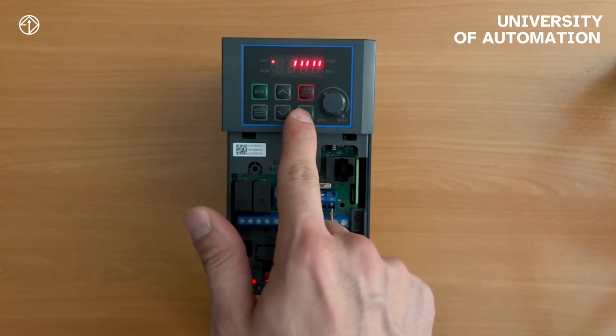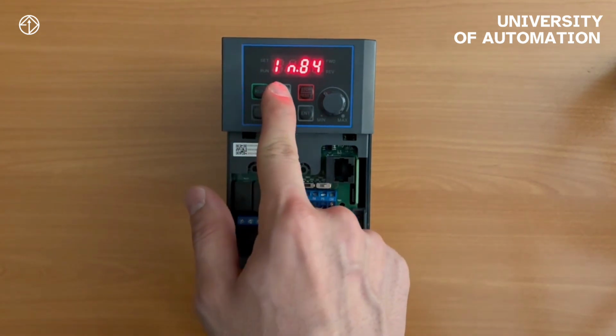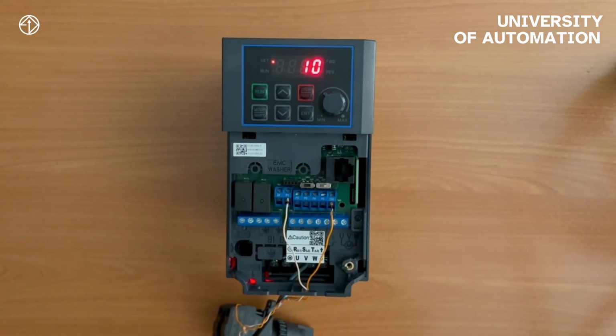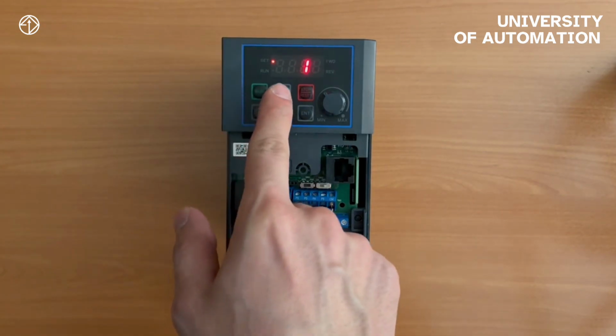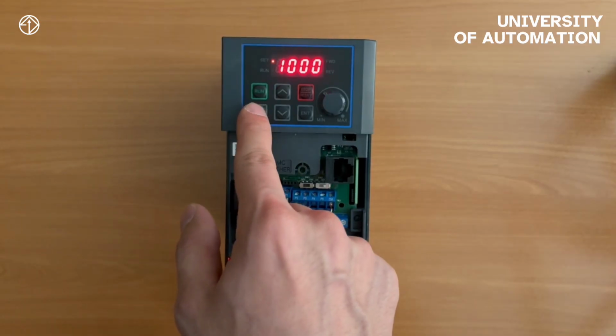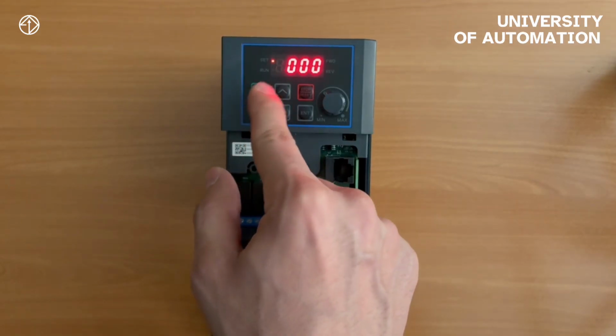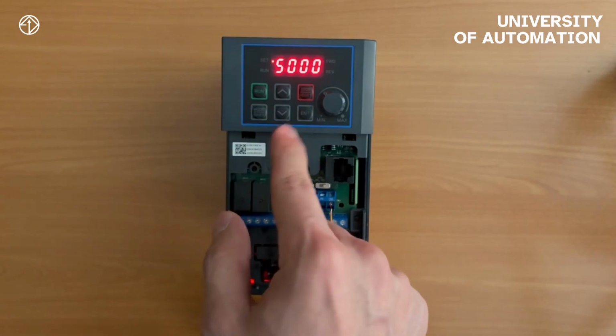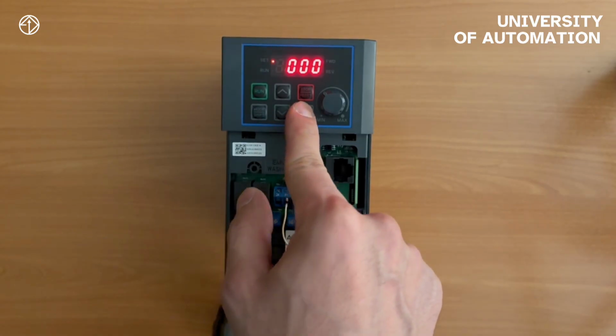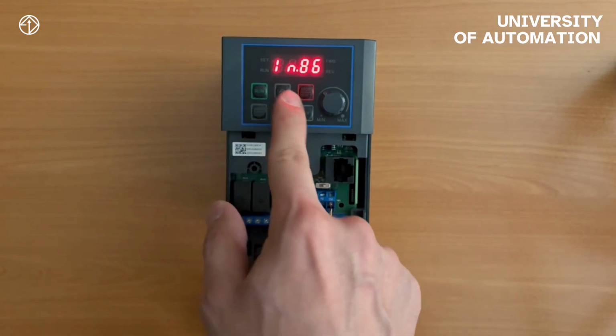We confirm it. All right, as we said, in parameter 85, we set the filter duration or the delay time for activating the digital input. For example, it's measured in milliseconds. For instance, here I set it to 5,000 milliseconds, which means 5 seconds.